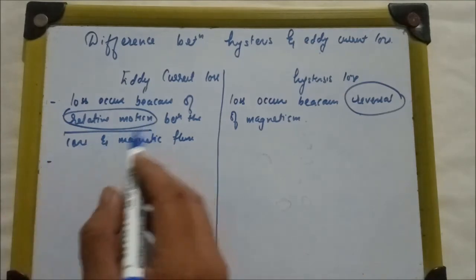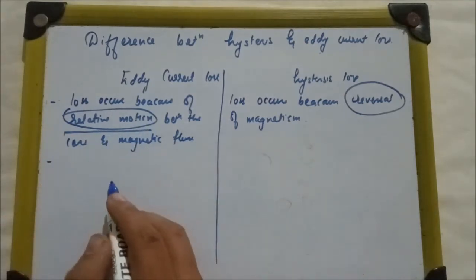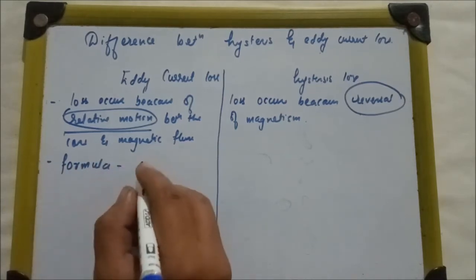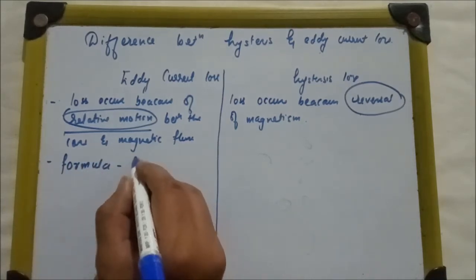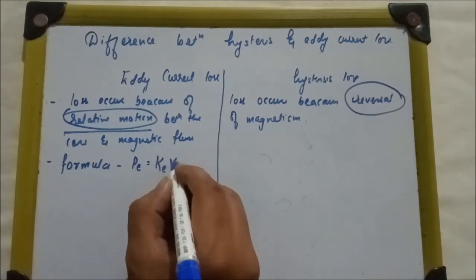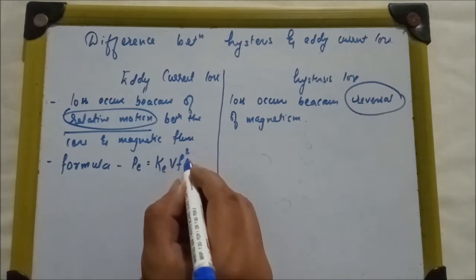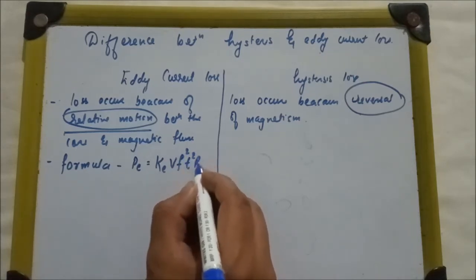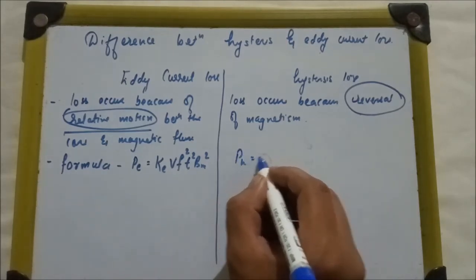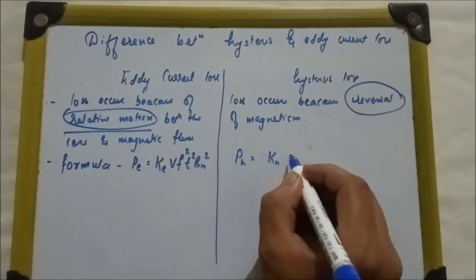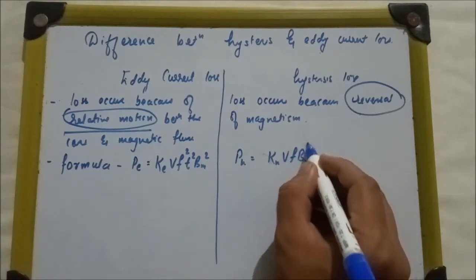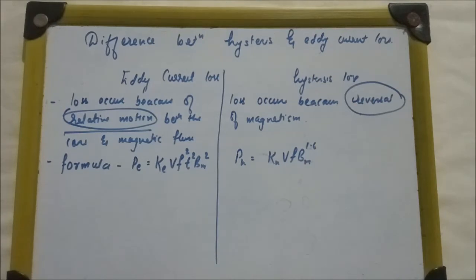So this is the definition of eddy and hysteresis loss. Now, what will be the formula? For eddy current loss, P is equal to KE V F squared T squared BM squared. The formula for hysteresis loss is KH V F BM raised to 1.6.